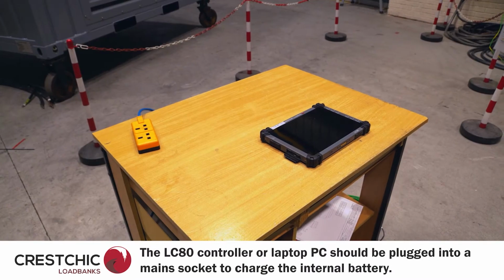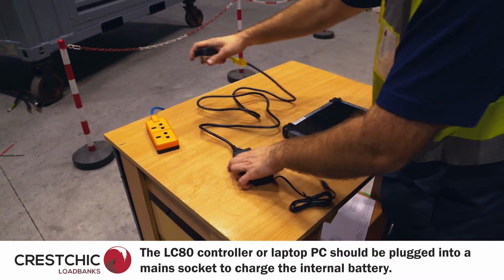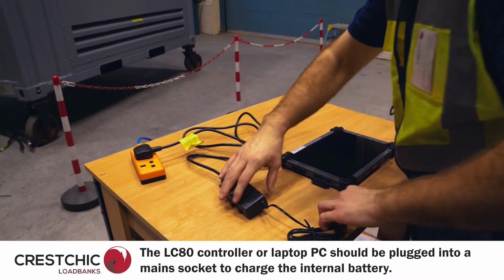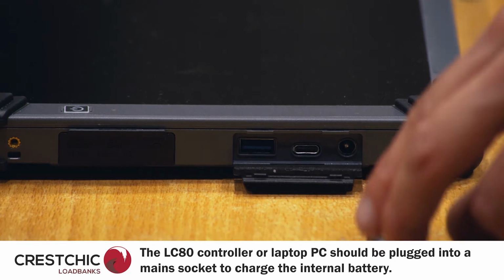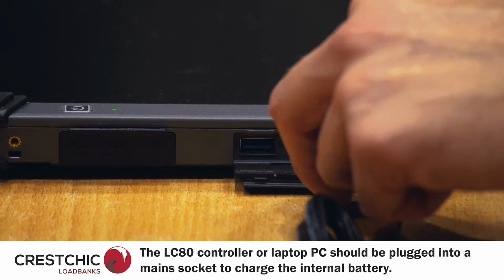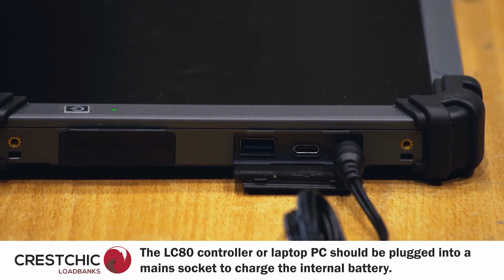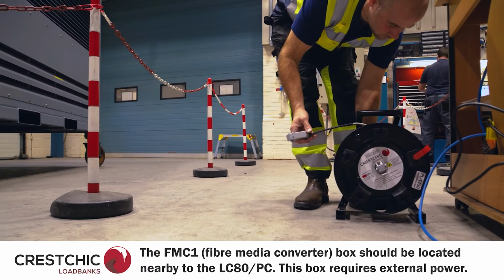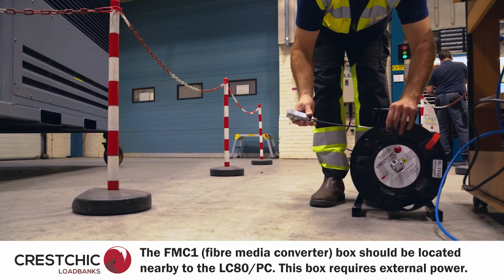Your load bank has probably been supplied with a controller to control the load bank. If this is the LC80 tablet or a PC, then this is a good time to plug the controller into the mains socket to charge the internal battery. At this stage, the controller can also be connected to the load bank.